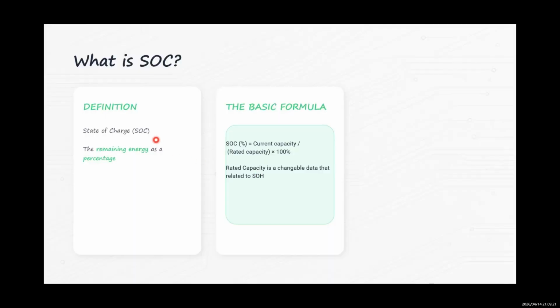What exactly is SOC? It is the remaining energy that tells you what percentage of energy is left. The formula is straightforward. SOC is equal to current capacity divided by rated capacity. But keep in mind, the rated capacity is a changeable data related to SOH.